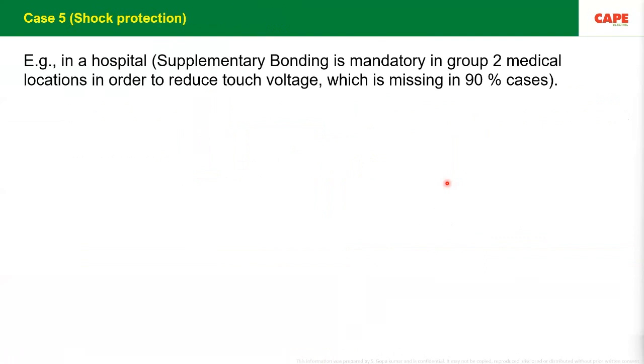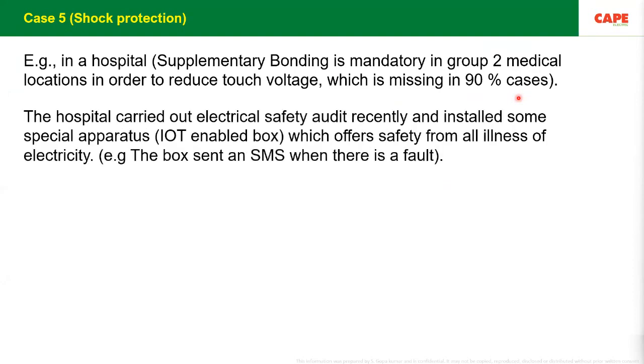Unfortunately, the system which we checked in a hospital, this interconnection called supplementary equipotential bonding is necessary in a group 2 medical location. Means in an operation theater, shock hazard is more dangerous because the patient, a lot of metallic items are bypassing the skin, resistances are lesser. You need to have a very, very high safety measure. Supplementary equipotential bonding is necessary. Unfortunately, this system is missing in almost 90% of the cases. During the last 2 years, I have visited at least 30 to 32 hospitals for making audits, and in 90% of cases this is missing. Other cases, of course, we are unable to test.